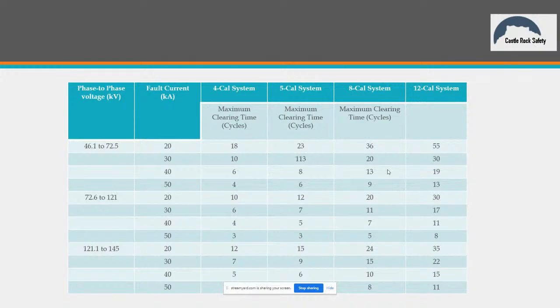So the distance that they use for this table is the MAD distance minus 2 times the arc distance. Okay, so let's say that you've got a MAD distance of 5 feet, right? And then you subtract from that 5 feet 2 times the arc distance. The arc distance is 1 inch for every 10,000 volts. Right. And that's to build a little bit of a safety factor in there.